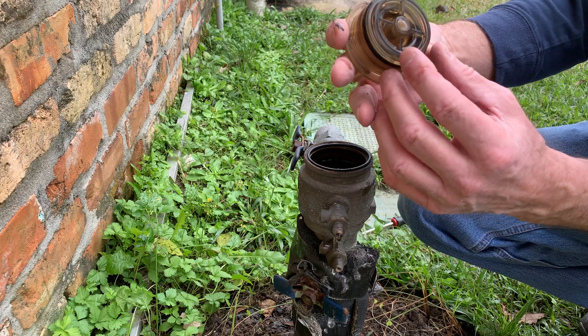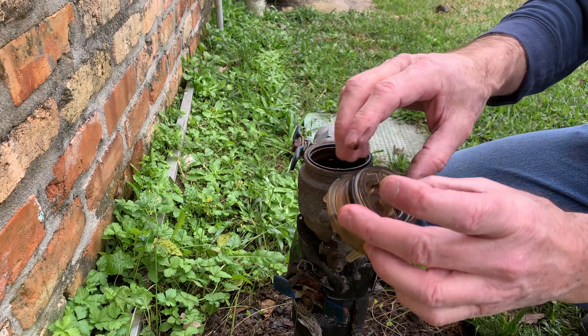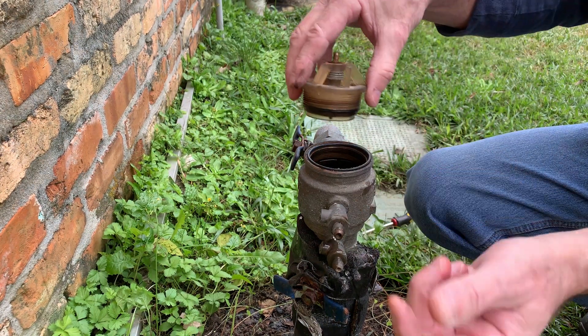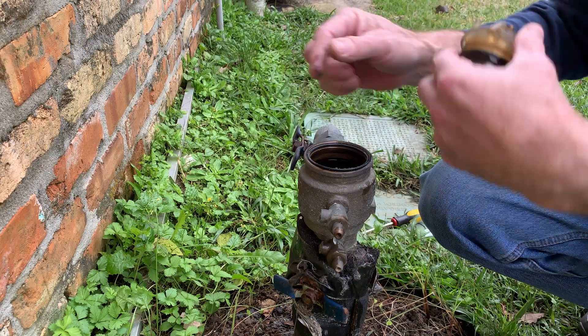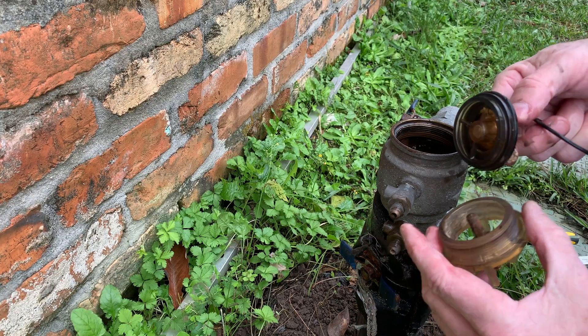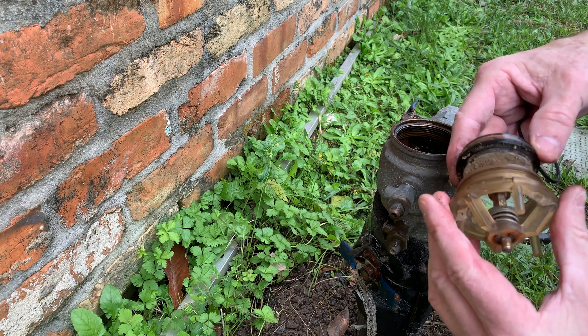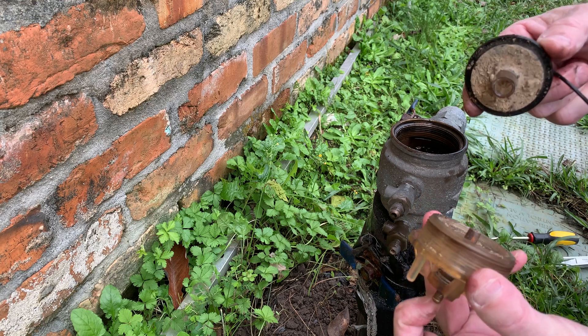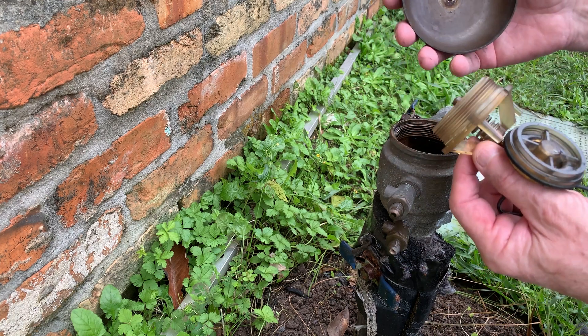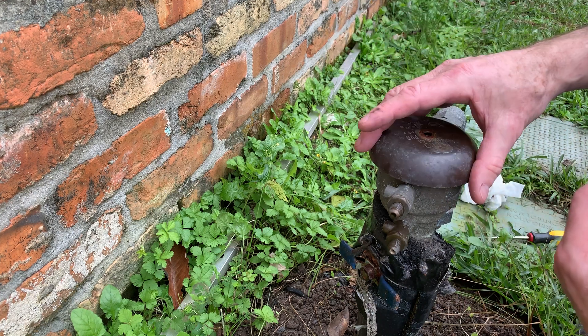What you have here is just a spring-loaded plastic valve that seals in here. It screws in. You have an O-ring here, the internal bottom part of the valve, and the upper spring-loaded stem. So if it froze, sometimes this will even be off of it, or you'll see water coming out underneath it.